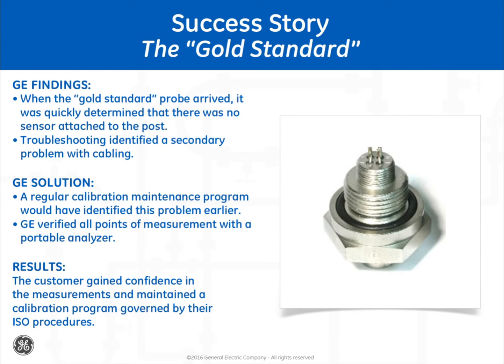The customer checked all points of measurement with a portable analyzer, cleaned up the installation of those that had issues, gained confidence in their measurements, and then went on to a maintenance program governed by their ISO procedures. This customer experience shows us the value of verification, regular calibration, and that the entire system should be investigated when issues arise, in this case, the interconnecting cable to the analyzer. Now let's talk about where to perform those valuable calibrations and how to manage them.